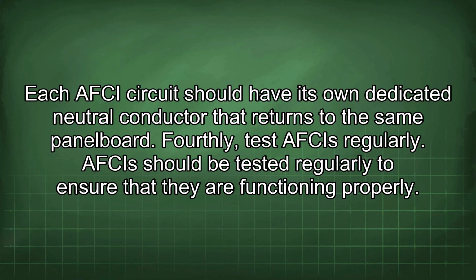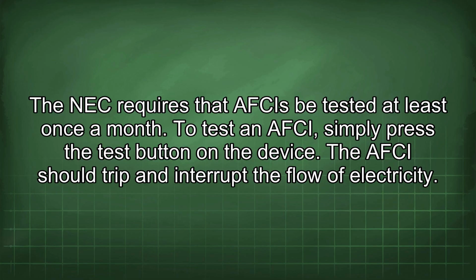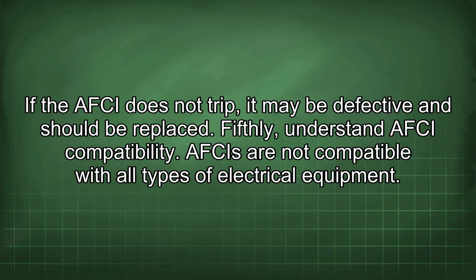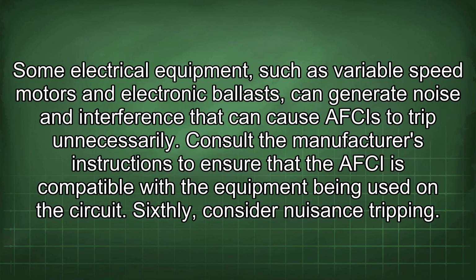Fourthly, test AFCIs regularly. AFCIs should be tested regularly to ensure that they are functioning properly. The NEC requires that AFCIs be tested at least once a month. To test an AFCI, simply press the test button on the device. The AFCI should trip and interrupt the flow of electricity. If the AFCI does not trip, it may be defective and should be replaced. Fifthly, understand AFCI compatibility. AFCIs are not compatible with all types of electrical equipment. Some electrical equipment, such as variable speed motors and electronic ballasts, can generate noise and interference that can cause AFCIs to trip unnecessarily.